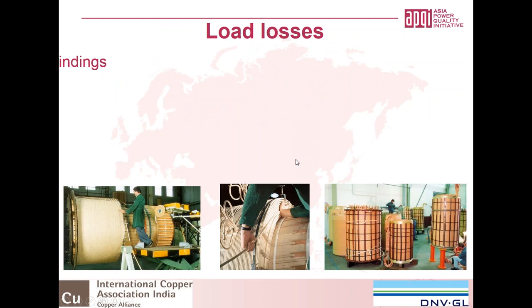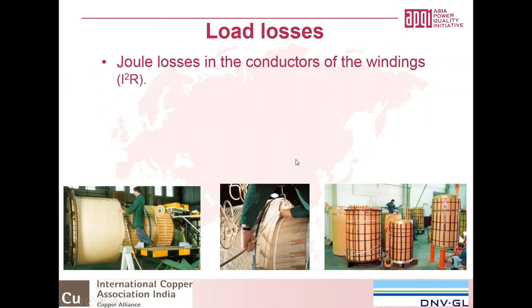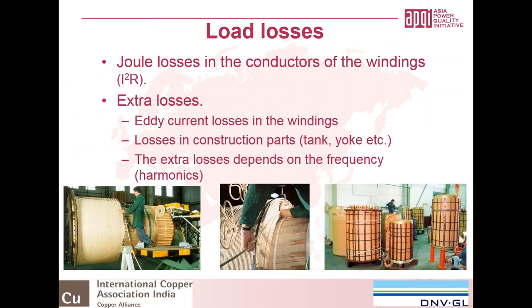Next to the no-load losses, transformers also have load losses, and basically the load losses that you have in the windings are Joule's losses, I squared R losses, or DC losses as they are often called, but we do also have some extra additional losses. I don't know if you have ever bought a transformer, and if you look at the reports from the testing, you will see that they measure the load losses with the Joule losses, and also mention extra losses. And those extra losses are within the winding, and they are caused by eddy current losses.